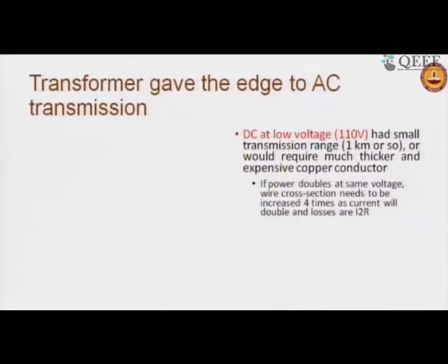On the other hand, it was felt that if the voltage was doubled from 100 to 200 volt, what will happen? If voltage was doubled to 200 volt, at the same power, the current will go down to half. If current goes down to half, the losses will go down by a factor of 4. So instead of 1 kilometer, one will be able to go to 4 kilometers.